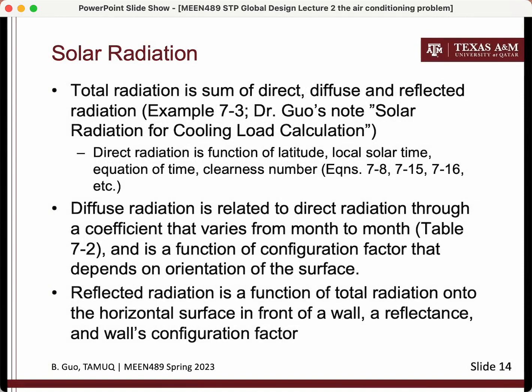For solar radiation calculations, some additional reading and learning will be necessary. In calculating solar heat gain through walls of a building, the sol-air temperature is used and the heat gain through each surface is calculated by applying the periodic response factor to account for unsteady heat conduction. The periodic response factor is a function of the wall's composition and dimensions and requires complex computation. Students are not required to calculate it themselves — it can be found through software, computer programs, or publications and textbooks.